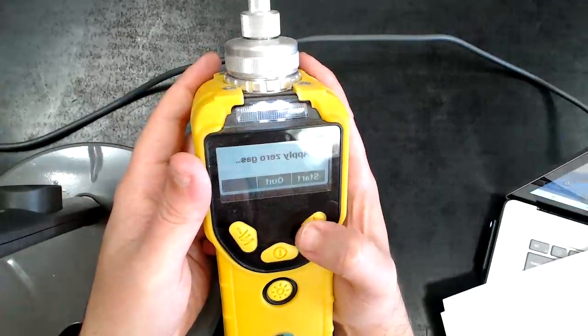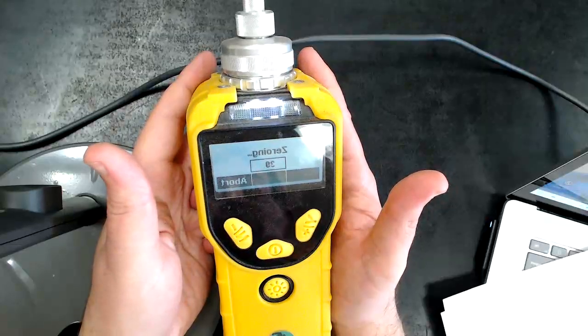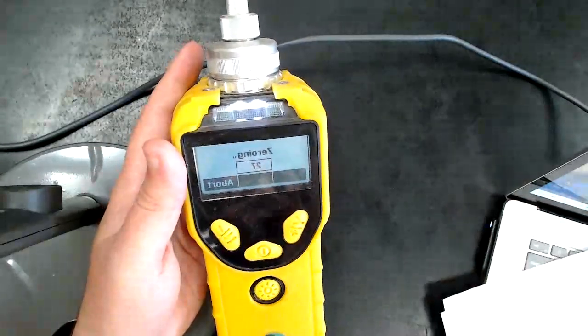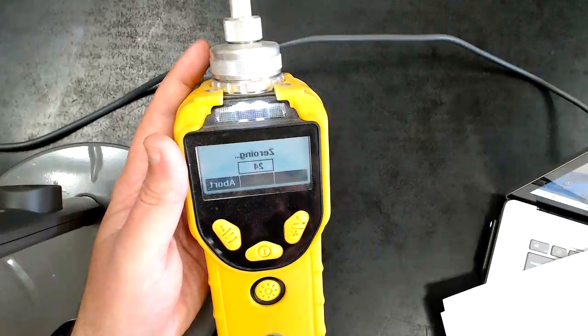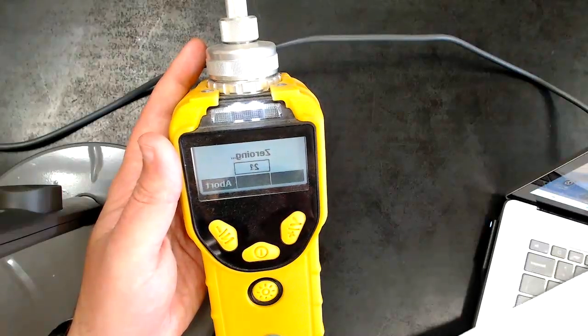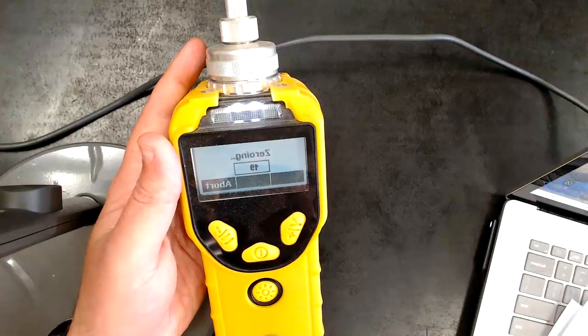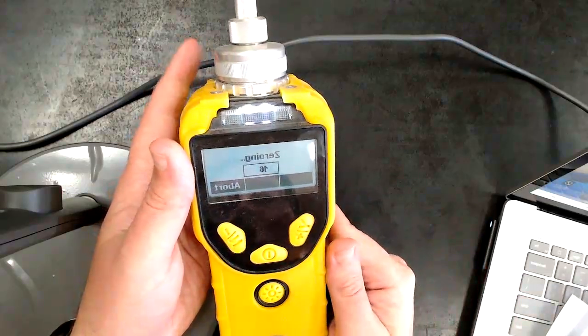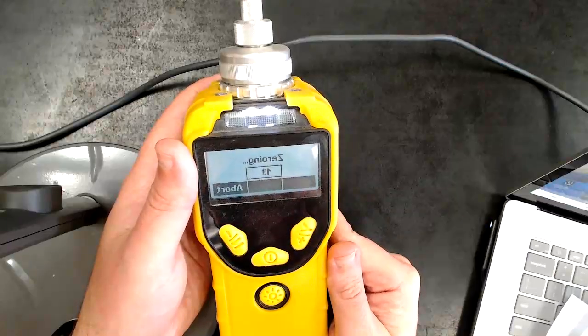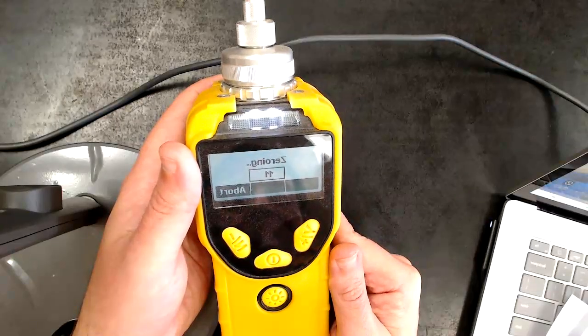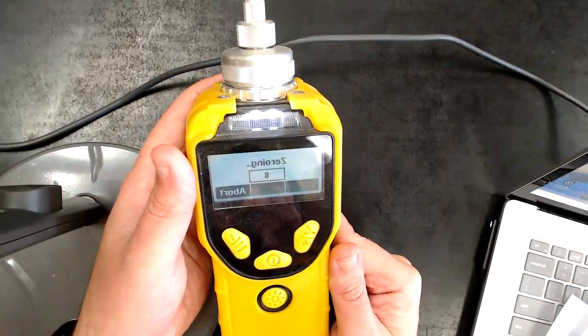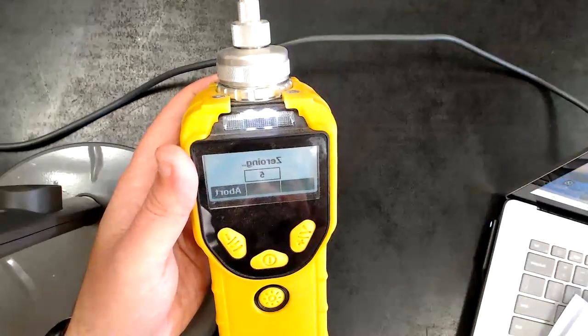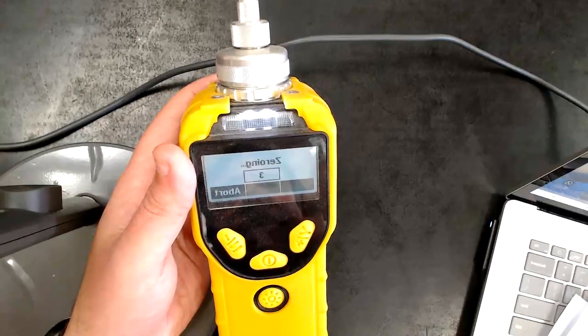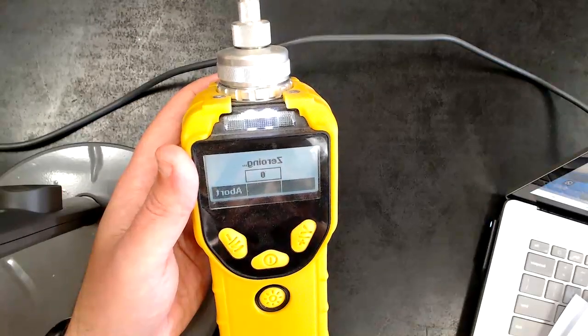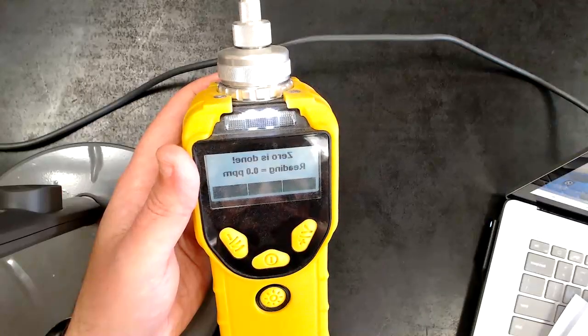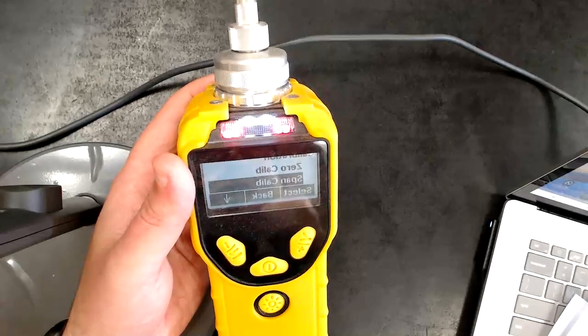It will start once you press start again. It takes 30 seconds to do a zero calibration. So we're just waiting. We've had this MiniRAE going for at least 5 minutes just to equilibrate. All right, it says done, so now we're at zero calibration.